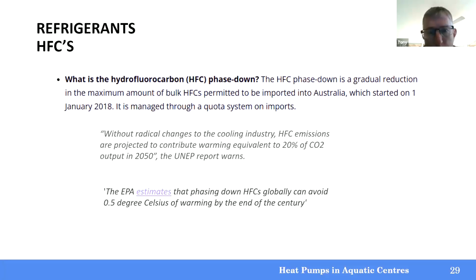Of the synthetic refrigerants, they started with CFCs, which as you know have been eliminated now. They moved to a version called HCFC, which is also no longer used. Then the next synthetic refrigerant invented was HFCs. Now it's been discovered that's not a very good option either, and throughout most of the world they've been eliminated or banned. In Australia, they've decided to phase down HFCs, and that's been in place since 2018.